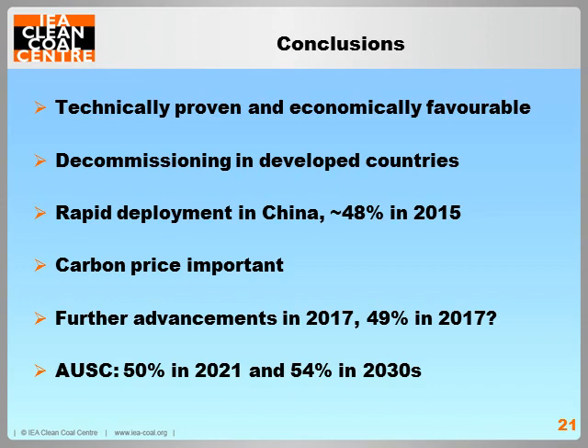Increasing costs associated with emitting carbon dioxide will favour double reheat technology in the coal industry. Improved steam cycles and unit configuration can increase efficiency to 48.82%, lower capital and running costs, and should be demonstrated in 2017. Finally, advanced ultrasupercritical technology using double reheat could reach 50% in 2021 and 54% in the 2030s.